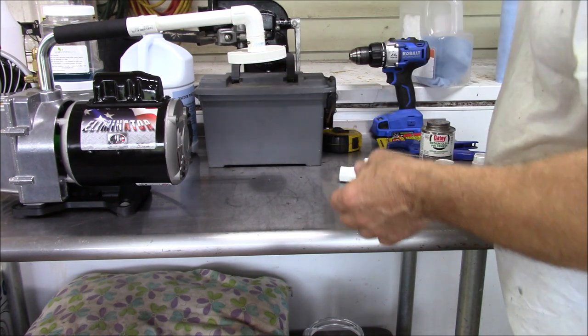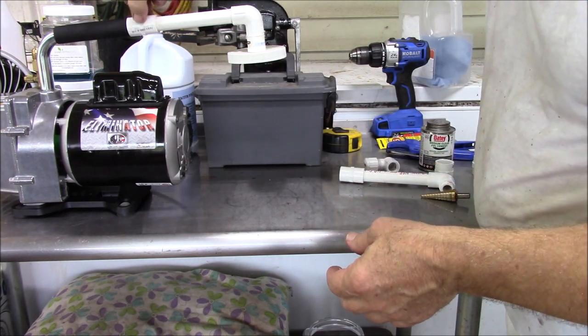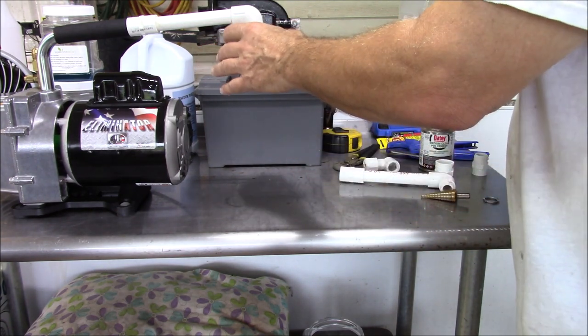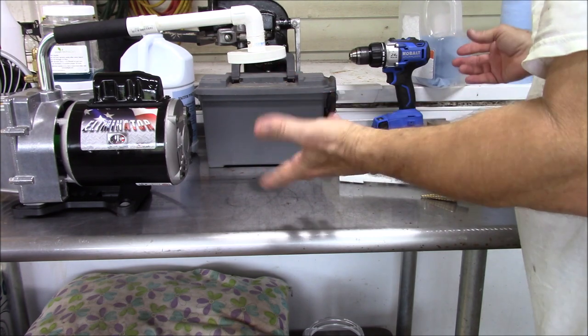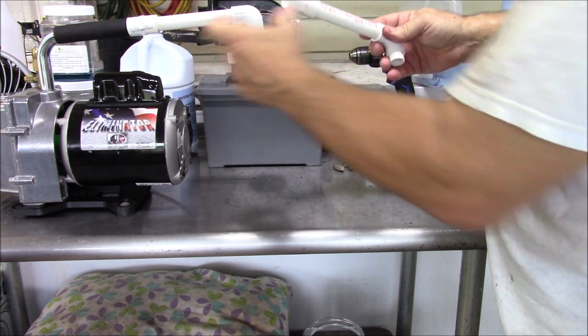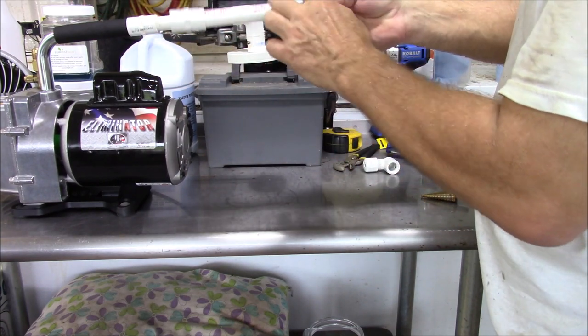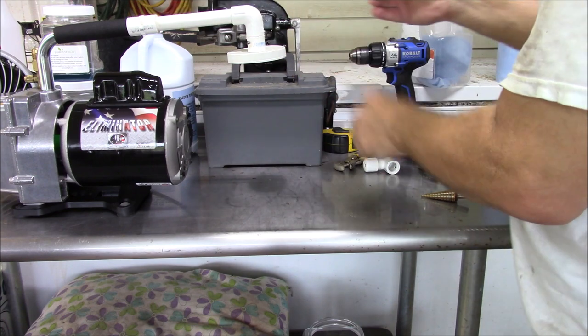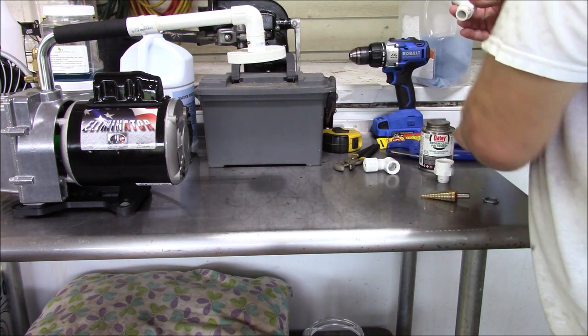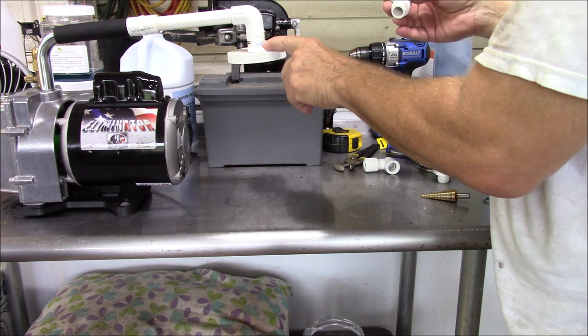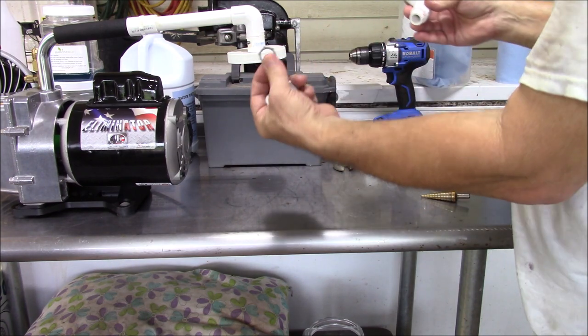And we used just a couple of pair of pliers to tighten this up. You can put a crescent wrench on it. That's probably the proper way to take and do it. And that's about it. The parts list, a threaded, because this will have the male threads. You need a female to a slip, to a 90-degree slip-slip, a short piece like this, and a slip to a half-inch threaded, and a nut. Put it together, and you're pretty much good to go.